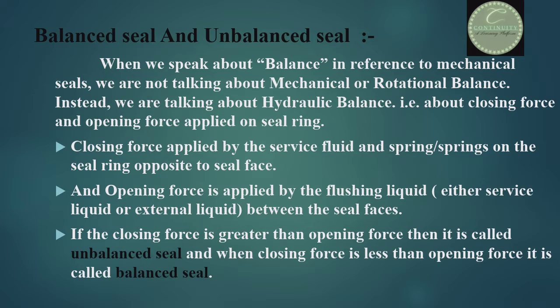What is closing force and opening force? Closing force is applied by the service fluid and spring or springs on the seal ring back to the seal face. And opening force is applied by the flushing liquid, either service liquid or external liquid, between the seal faces. These closing force and opening force decide whether the mechanical seal is a balanced or unbalanced type. If the closing force is greater than opening force, it is called unbalanced seal, and when closing force is less than opening force, it is called balanced seal.